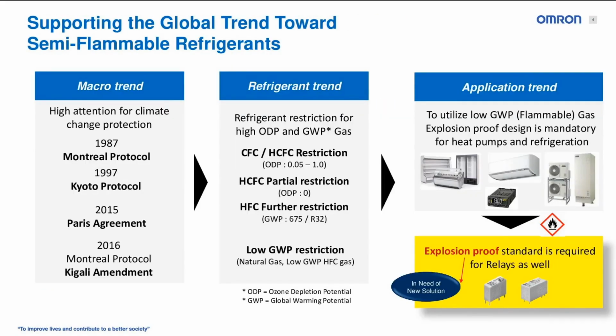So to support the global trend of semi-flammable refrigerants, we look at the macro trends that exist. We have the Montreal Protocol, the Kyoto Protocol, Paris Agreement, Kigali Agreement. All of these relate to climate change protection and mandate certain gases and refrigerants that can be used to better the environment. That refrigerant trend is reducing the ozone depletion potential limit that we allow in such refrigerants. So we're moving to a safer refrigerant for the environment, and it also lowers the global warming potential, which is GWP.